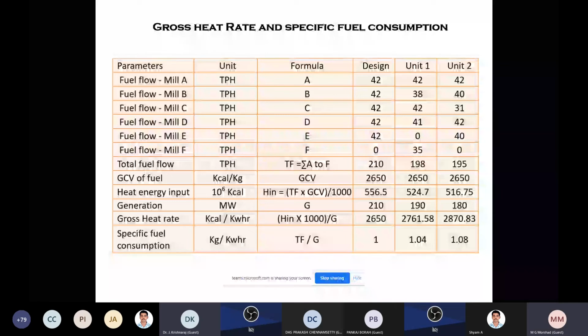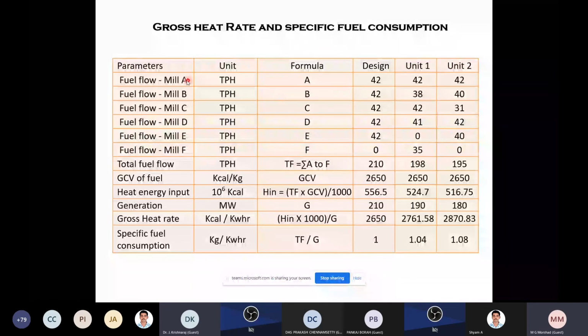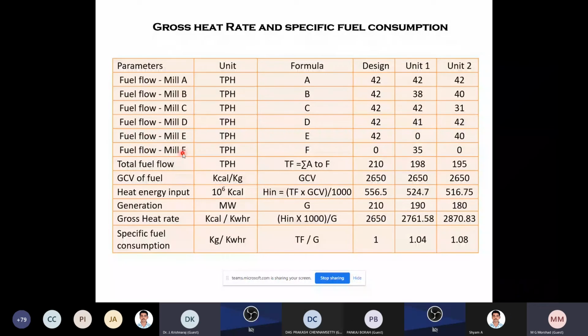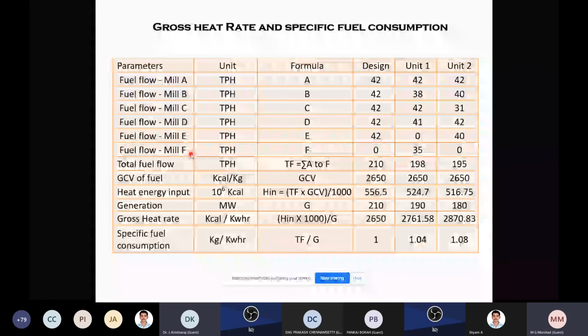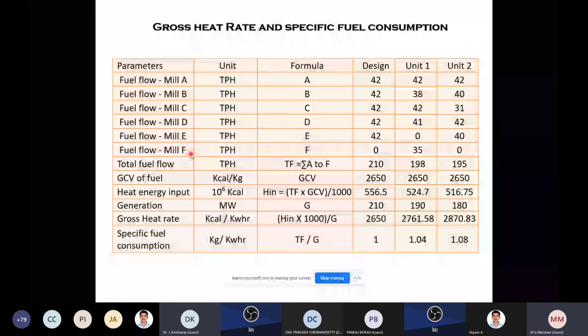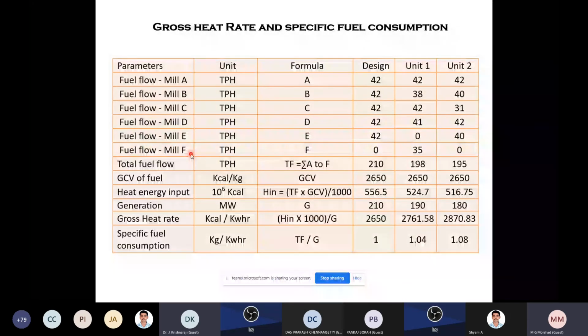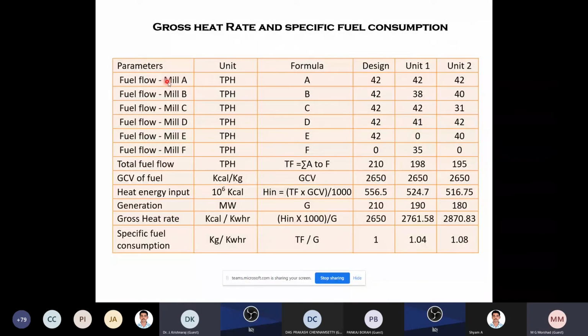Now, how to get the gross heat rate and the specific fuel consumption. First, each mill will be delivering some lignite or fuel. So mill airflow, fuel flow, mill A, B, C, D, F. We are talking about the pulverized mill, which is not a ball mill. It is not there; it is available in the coal plant. I am telling about the pulverized mill, which is available in the lignite fired boiler. So whatever the mill is, you can establish the flow in ton per hour for unit 1 and unit 2, and the total air flow and total fuel flow you can establish.